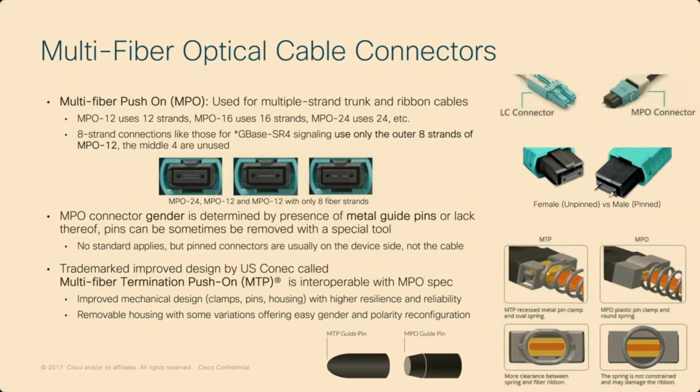But one of the things that you should be getting used to, if you have not been working with them in your data center yet, is the multi-fiber push-on connector. The reason for this is that most of the signaling standards out there today that have gone from the 100 gig speed range up into the 400 gig and then on into the 800 gigs are going to be using more than two pairs of fiber. So in order to support those, we have what's called a multi-fiber push-on, or MPO.